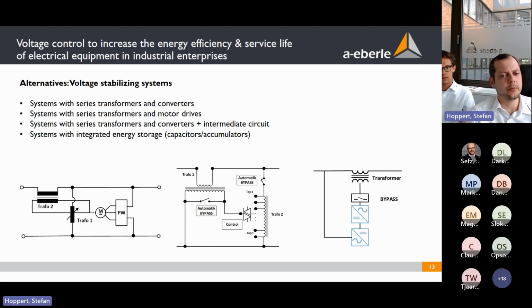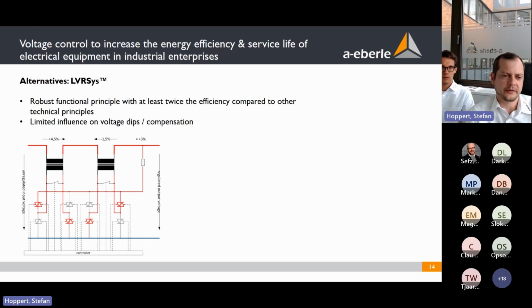So when we are competing and comparing ourselves to this kind of technology, we see that due to our principle, our power loss is half of them. So it's half of the competitors. The reason is that we have the transformers just in the mains, in series with the main line. So we do not control a transformer which controls a transformer, we control the transformers directly in the mains. And that means the power loss is more than half less compared to competitors. And this kind of principle is really robust and with a long lifetime.